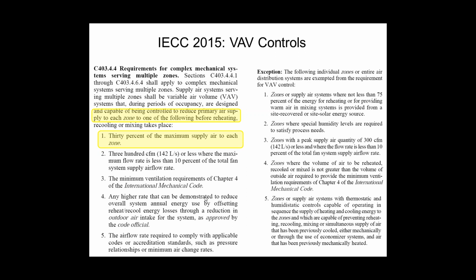So you can't take a hot deck and a cold deck and mix them anymore. But if you have reheat on a VAV system, you're allowed to run the reheat even when the air handler is in economizer or in cooling mode, if you follow certain rules. The big noted rule from a control standpoint is you have to first throttle the CFM of that particular VAV box down to 30% of its maximum design airflow. Then you can start opening the hot water valve or staging electric heater. And then if you need to, especially with electric heat, you could start increasing the CFM to keep the heaters online if you had to. But you first got to throttle everything back.